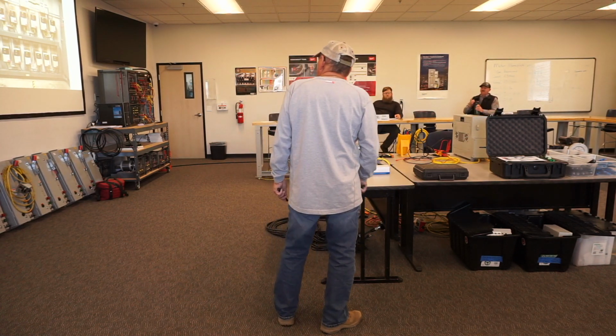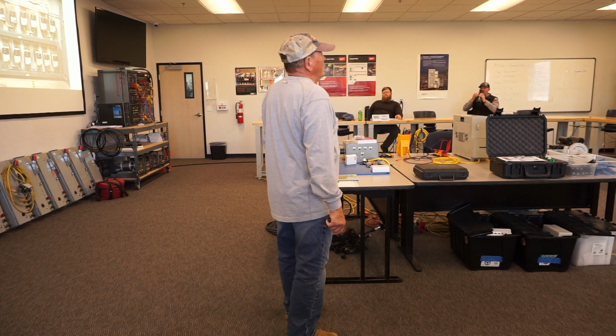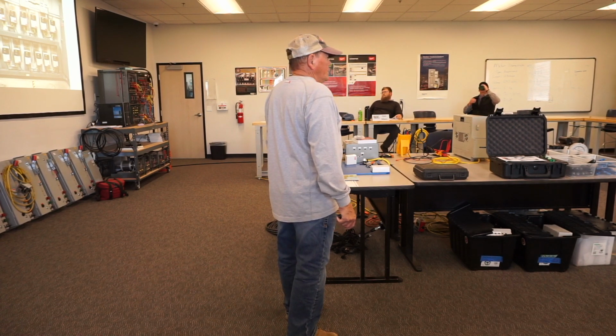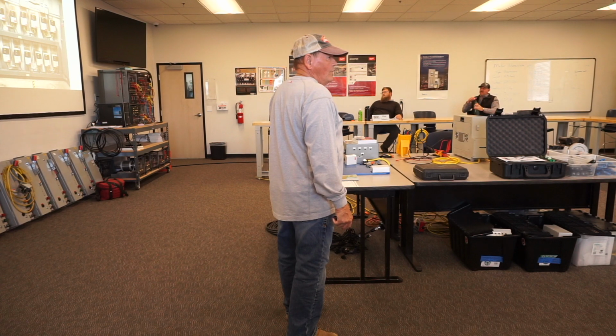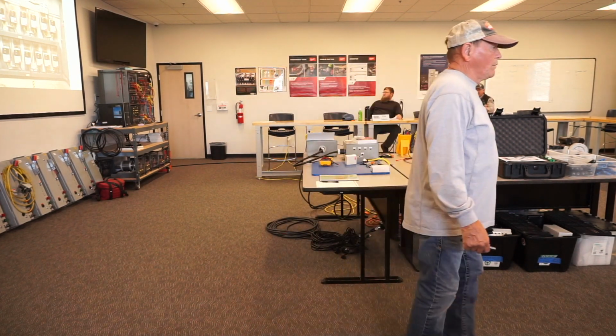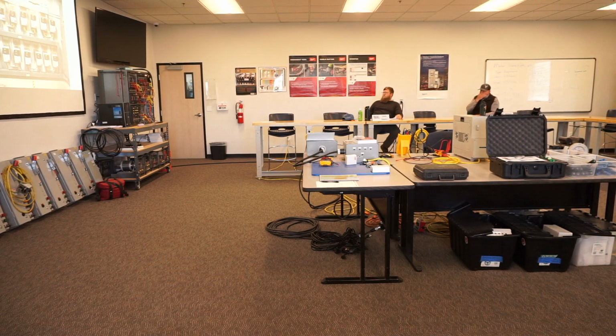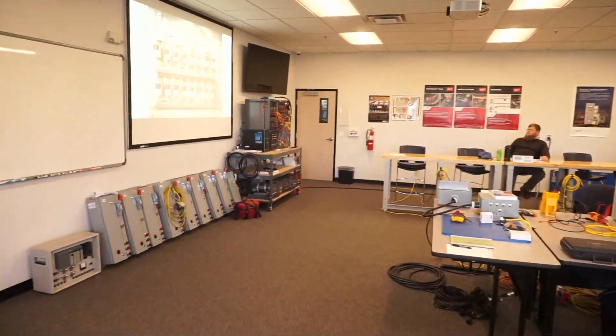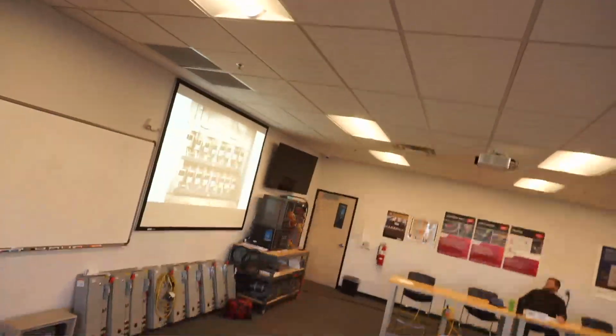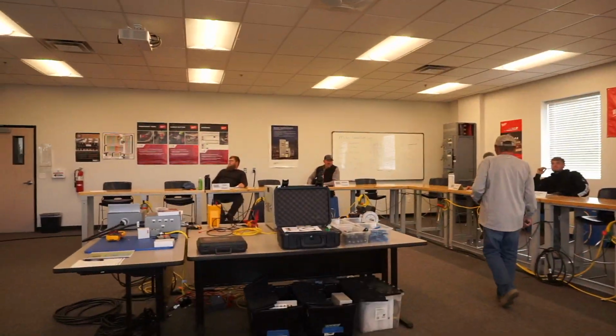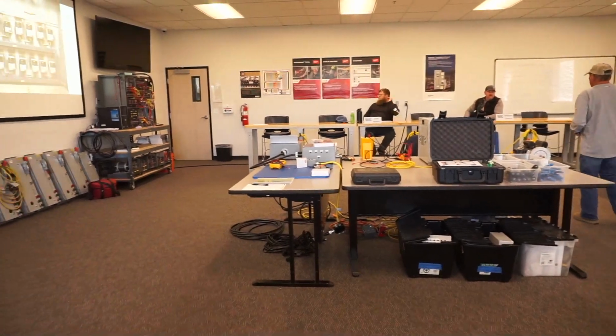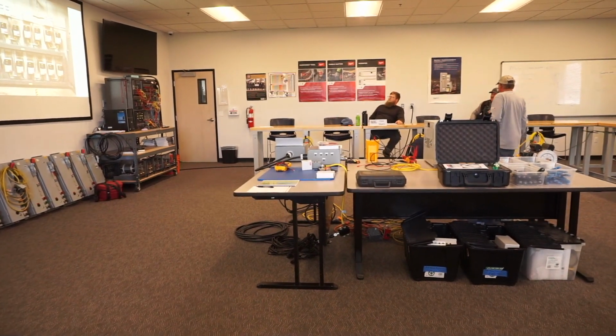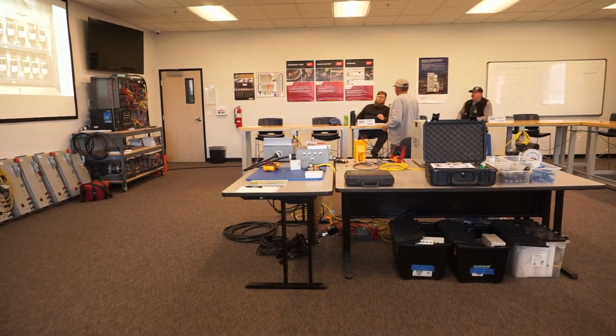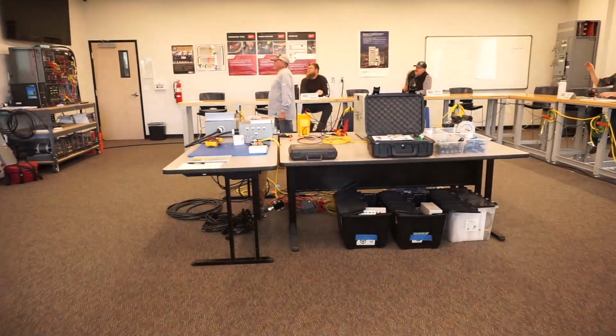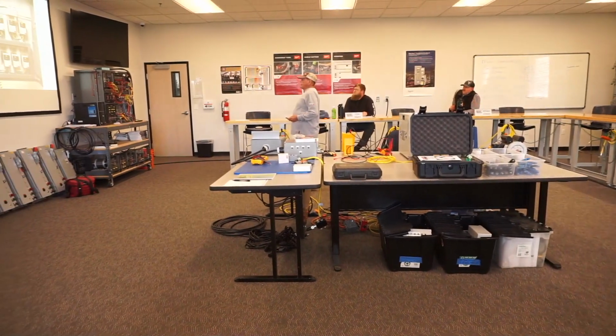So they take me to this electric room, and I look and I said, oh, there's your problem. Anybody see an issue? The gutter looks illegal to me. The gutter. What's the problem? With the 30 current carrying conductors in the gutter, right? 30 current carrying conductors going across the field gutter. I'm sure you guys are probably not aware of the standard installation practices for variable speed drive. Do you recognize it? How about you? You recognize the problem? Mixed in the same gutter. Okay, standard practice for installing drives, right?